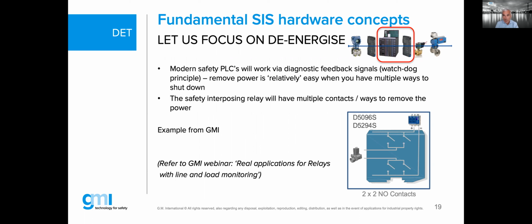Again, we will not go more in depth about this, but now we come to the final element, and to the final conclusion. We need to remove the power to the final elements over here. I give you here an example of two different types of interposing relay from GMI, which are specific model numbers, and that's typically known as NO, which stands for normally open contact. So the safety function of the interposing relay is to remove the power. In case you are removing the power on the inlet, the input of the interposing relay, then the output has to be built in a multiple fashion, as they show over here, to remove the power.